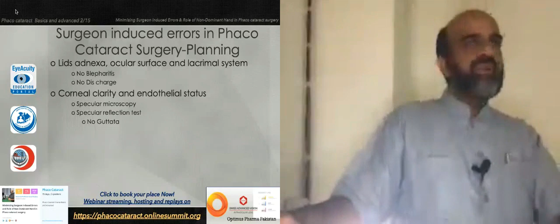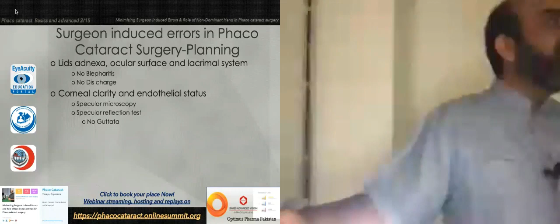And the cornea will decompensate at what level? If it is less than 1000, compromise starts. Less than 700, it will be difficult to keep the cornea clear. So if you don't have a specular microscope, what is the other alternative? A simple one, that is known as the specular reflection test. It is a very simple test.